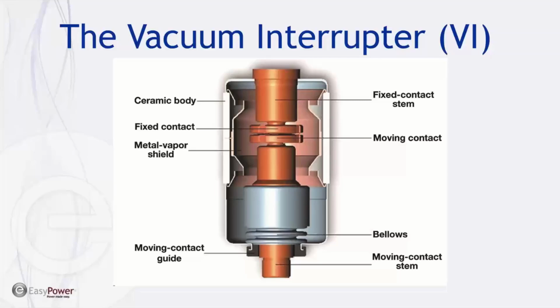There are also a series of what are called metal vapor shields inside the vac interrupter. So these shields are very important because over time, metal vapor will be deposited from that interruption of the electrical arc, and that metal vapor, if the shields weren't there, could potentially be deposited on the inside of that ceramic body, which is providing the insulation. So if enough metal vapor collects on that ceramic body internally, you would have an internal short circuit. So those shields are there to act as a barrier and to be a place that metal vapor can be deposited, that prevents it from being deposited on the ceramic body.